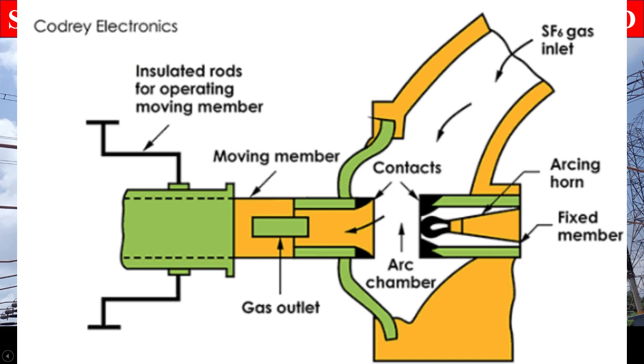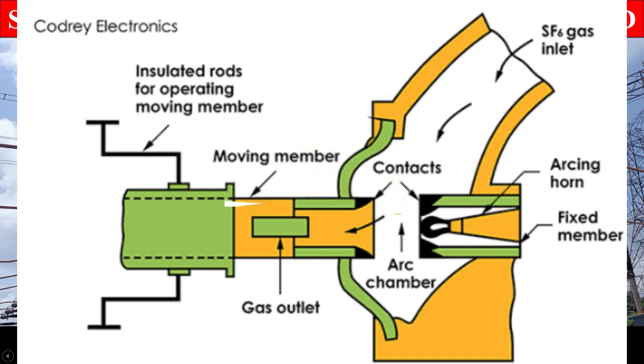Construction. It consists of fixed and moving contacts enclosed in a chamber called the arc interruption chamber, containing SF6 gas. This chamber is connected to an SF6 gas reservoir. When the contacts of the breaker are opened, the valve mechanism permits high-pressure SF6 gas from the reservoir to flow towards the arc interruption chamber.